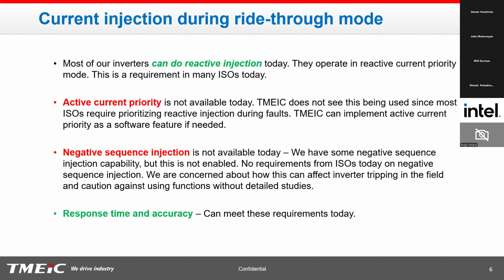So we are definitely concerned about how this function, if enabled, can affect inverter performance during ride-through events, and we don't have extensive experience with power system studies with this function. So currently we are not enabling this. We would wait for more guidance from the ISOs on how to study this, how to test this, and how this is going to be beneficial to their system. We're waiting on that portion to be discussed in ISO requirements.